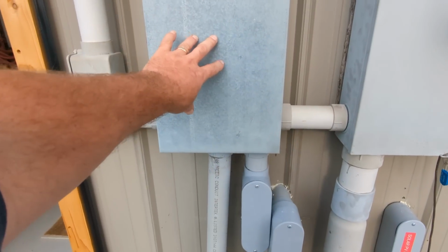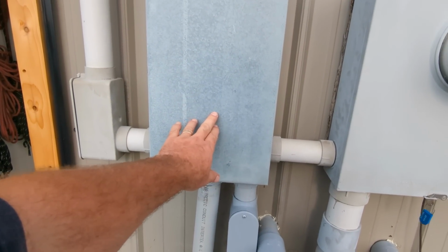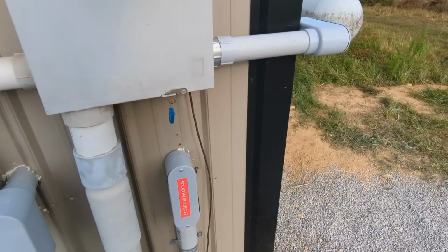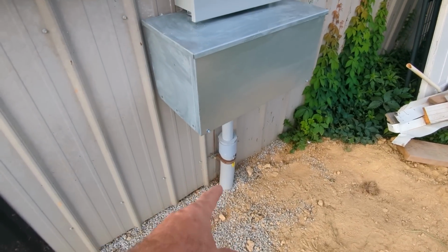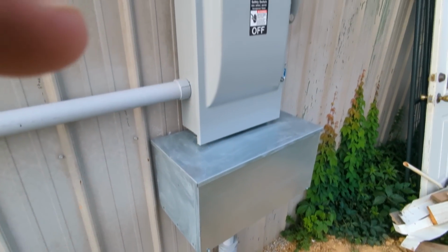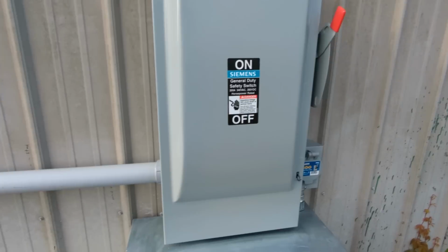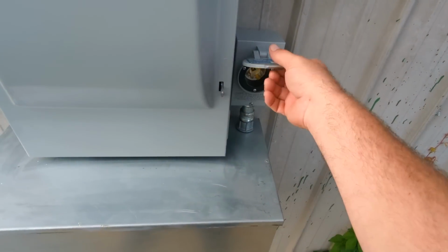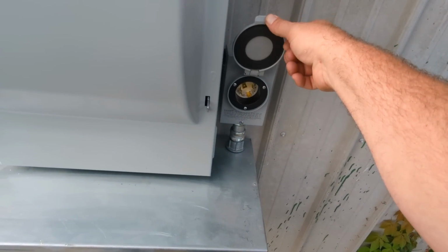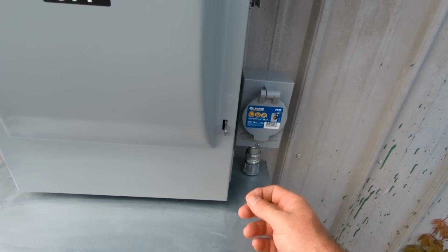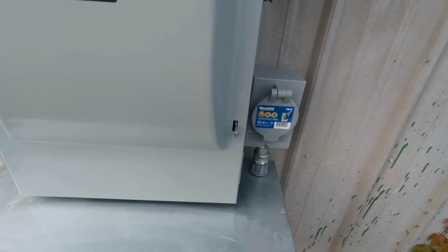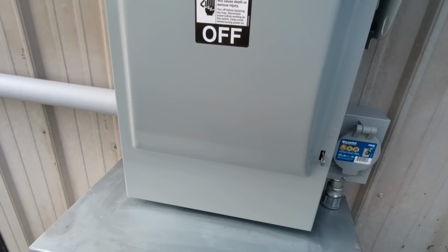We're feeding this panel, which has RV. And then the conduit here goes to the house, and that's fed off of that power distribution block. And again, here's our AC disconnect. And then a fail-safe backup. He has a 7,000-watt Honda with an L14-30 30-amp plug here, so he can get his batteries out of trouble in a grid-down situation if he's using a ton of power.